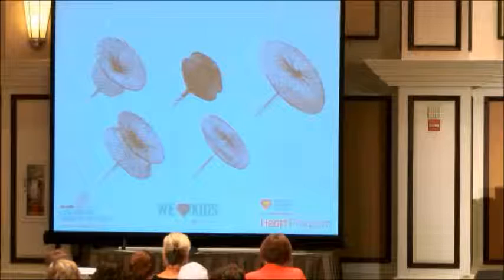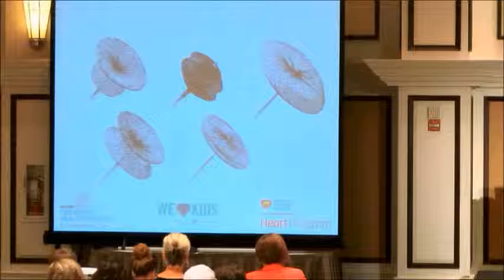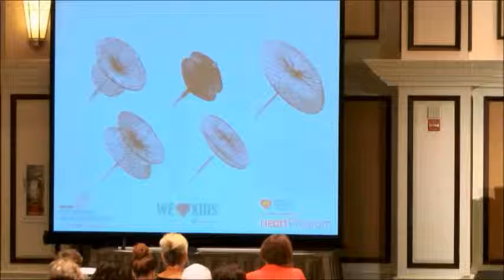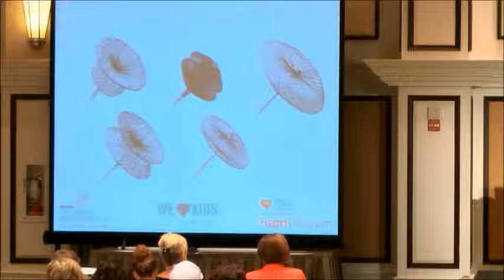This is an array of what the devices look like. The one thing they have in common — what transcended medical care with transcatheter techniques — is they're made of nickel titanium, which you pronounce 'nitinol.' Nitinol has shape memory. Once that hit the medical device market, you could make something any shape you want, pull it down into a catheter straight and linear, put it in, and when it comes out of the catheter it goes back to its intended shape without distortion. Once we had a metal with shape memory, it totally changed what we could do in medicine.